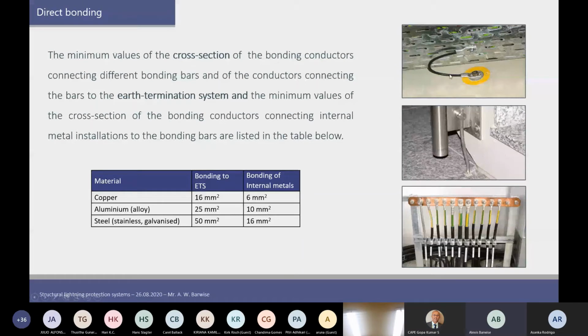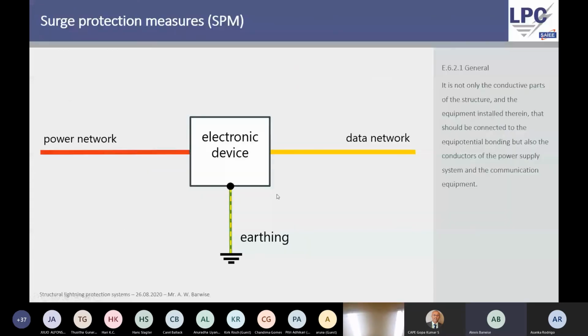The last part is that we have to do direct bonding. So the surge protection is the indirect. Direct bonding looks like this, where we are ensuring bonding from cable trays to the down conductor or earthing system, bonding of rail lines which we can touch, railways. We have also here the earth bar which we showed earlier, and a very simple understanding as to the sizes are given again. If you are bonding between earthing terminals, earthing bars, we have to have at least a 16 mm squared. If we're only bonding internal metal parts like here, then we need at least a 6 mm squared, so a lesser rating. And that's it.